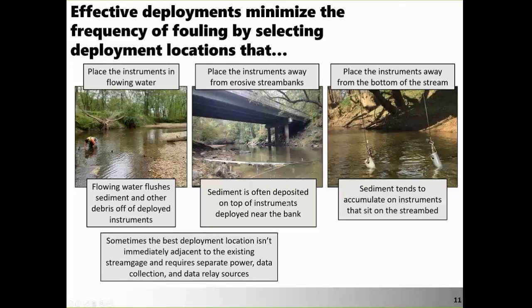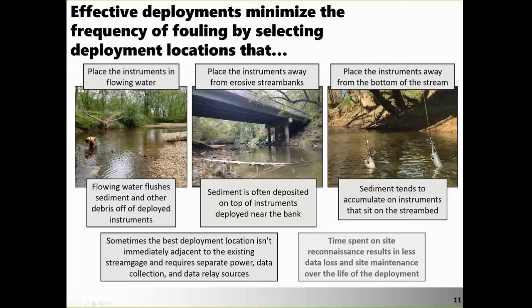Sometimes the best deployment location is not immediately adjacent to the existing stream gauge and requires a separate data logger and power source. It's often worthwhile to make that sacrifice to find a location providing maximum data quality. All time invested in site reconnaissance results in less data loss and less site maintenance over the lifetime of the deployment — reconnaissance is a crucial part of an effective deployment.